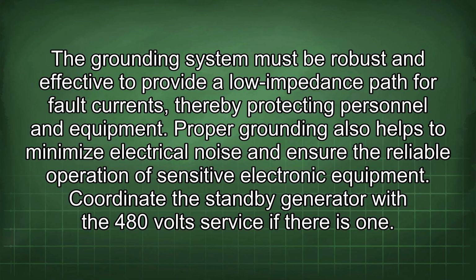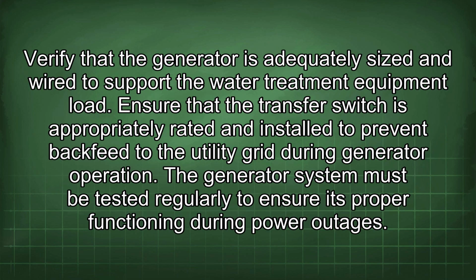Coordinate the standby generator with the 480 volts service if there is one. Verify that the generator is adequately sized and wired to support the water treatment equipment load. Ensure that the transfer switch is appropriately rated and installed to prevent backfeed to the utility grid during generator operation. The generator system must be tested regularly to ensure its proper functioning during power outages.